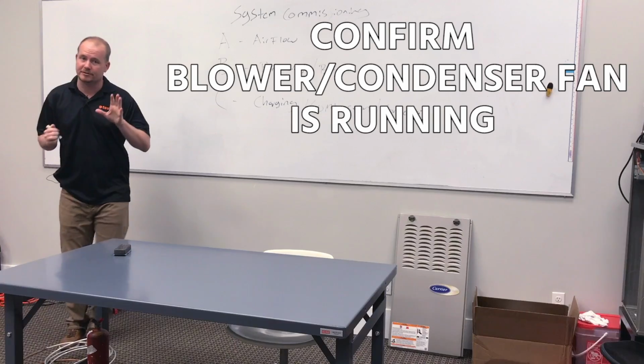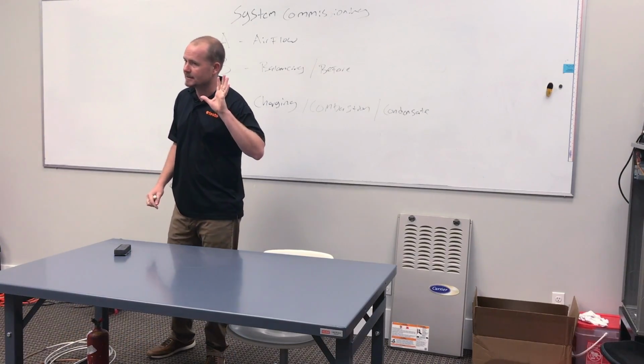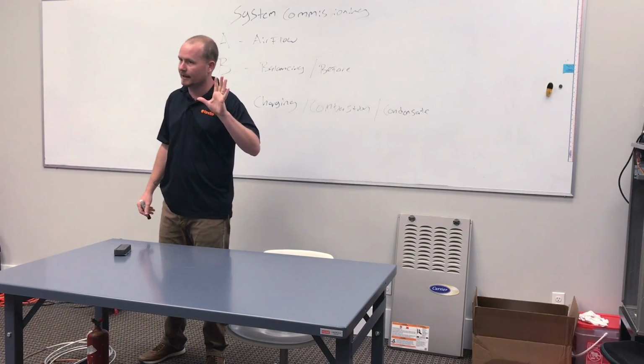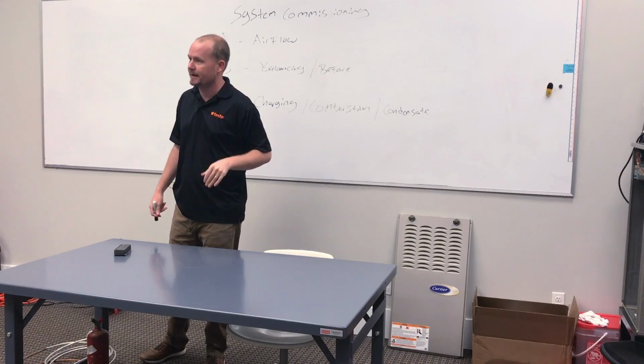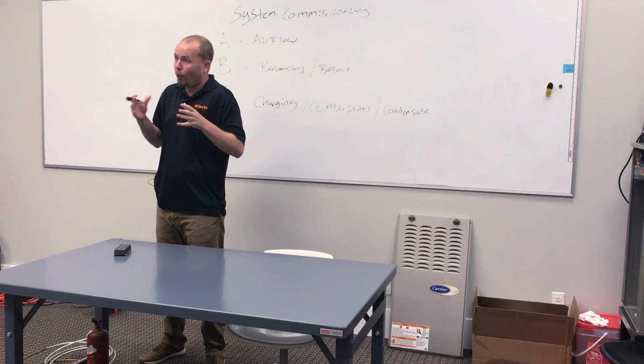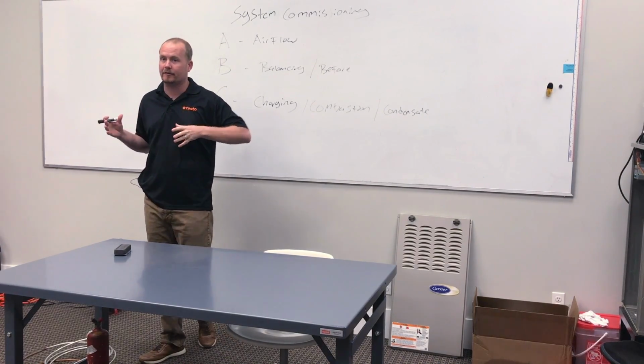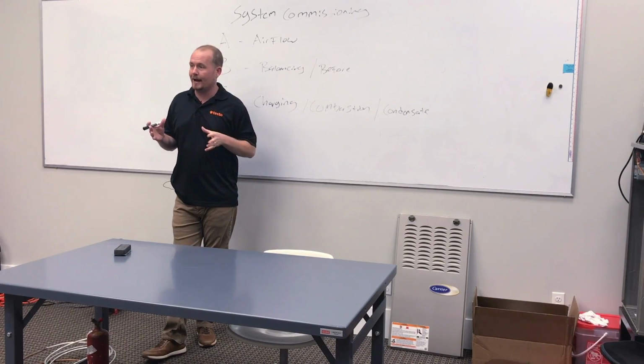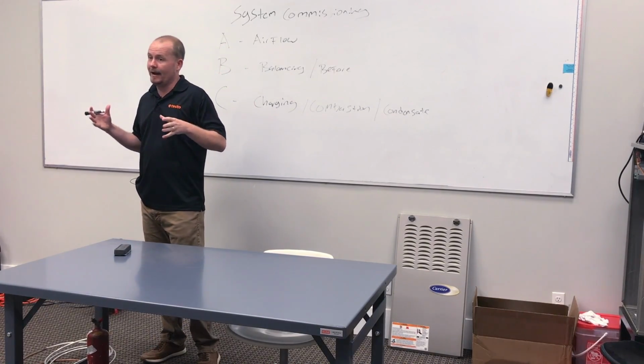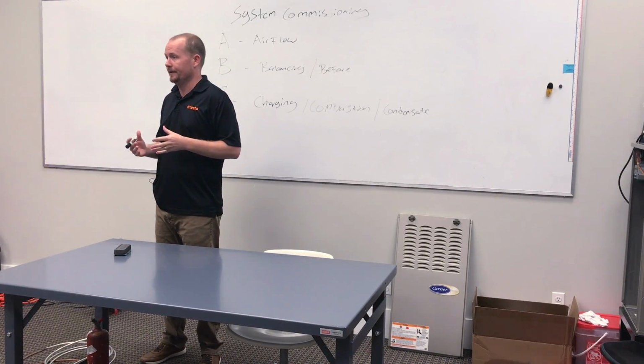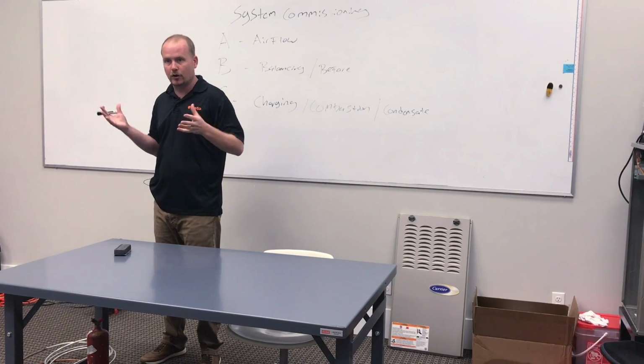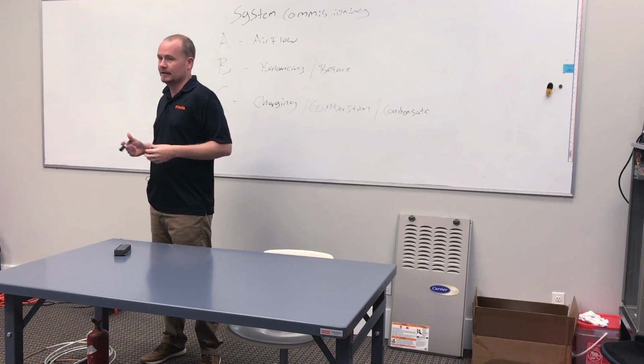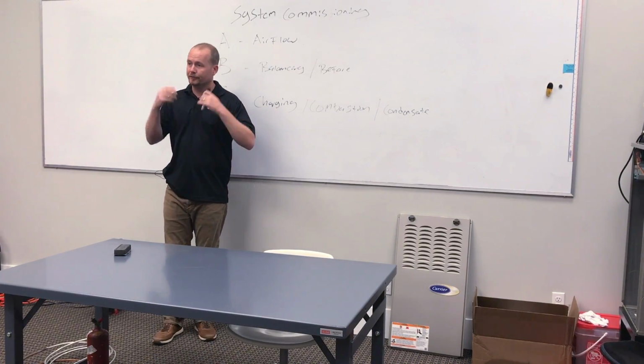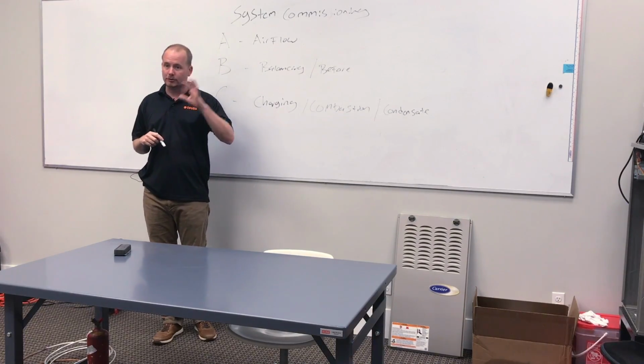And not even just blower's running, but blower's running and it sounds normal. It sounds like a blower that's running up to full speed, or it doesn't sound like it's sucking air in from every hole in the cabinet. Because that happens when you have airflow restrictions, especially with variable speed motors where they're trying to draw air and you've got a dirty filter or some sort of airflow restriction, right? So if you listen to enough of them, you notice those things. So you don't skip that step.